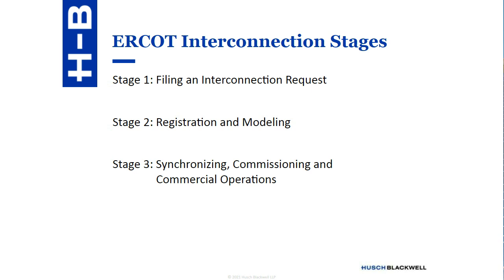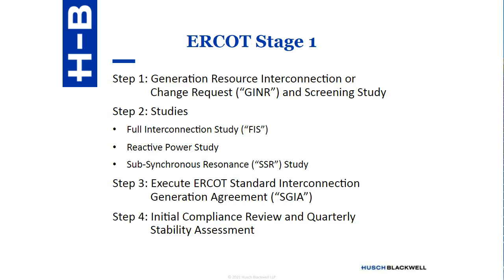The third stage is the physical interconnection process itself: energizing, synchronizing, commissioning, etc., and the various approvals and tests that go with these activities. At the completion of this third stage, the project is given a resource commissioning date and is fully commissioned on the ERCOT grid. The first part of stage 1 is the submission of what's called the GINR, and that stands for the Generation Resource Interconnection or Change Request.